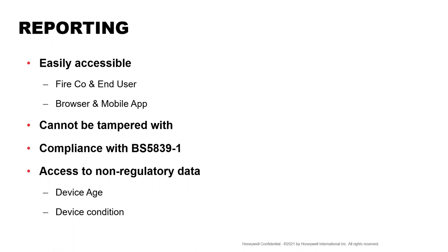There are times and occasions when an engineer will rock up to site to do a service and he's expected to do 25% of the devices that are in that building. Well, he can't get in three or four of the rooms because there's a board meeting going on. If it's in a hospital, there are several occasions we have this all the time. They try and get in to do the testing and whatever, and they can't. It might be an operating theatre, which is in use. So they get to the end of the year, those devices haven't been tested. If we're looking at the letter of the law, in theory, that's non-compliance. With the information that we're talking about now, that can be controlled.